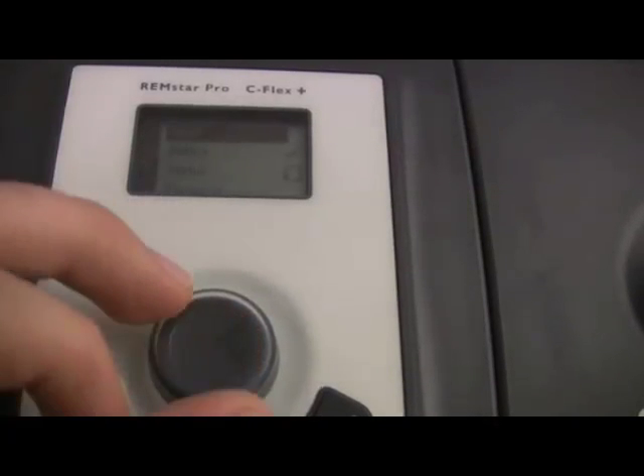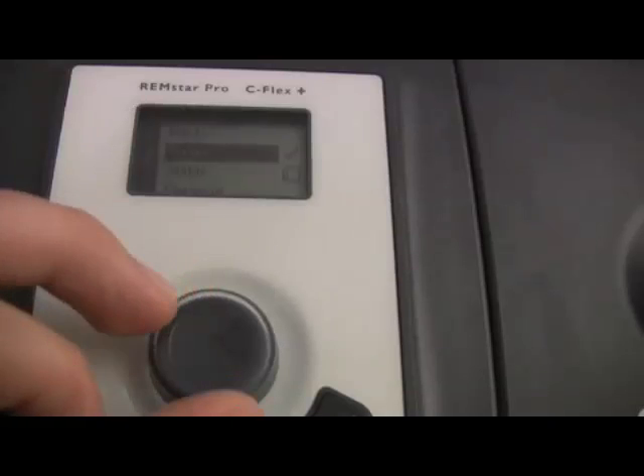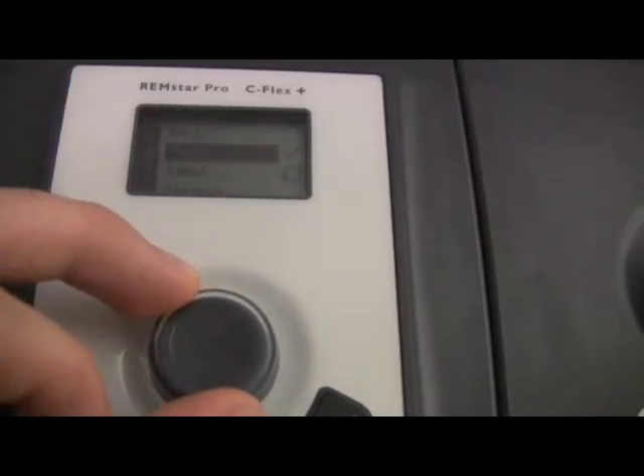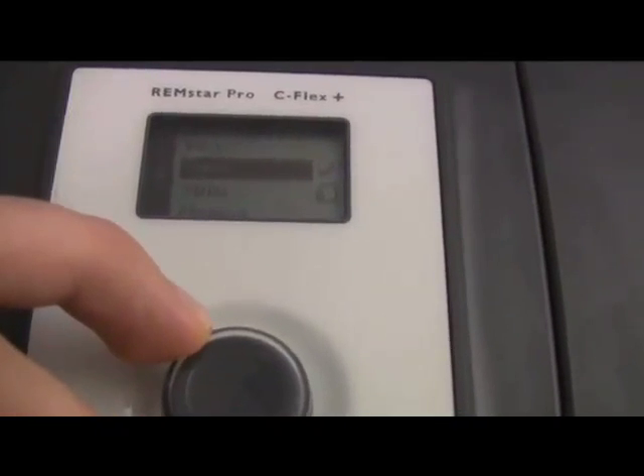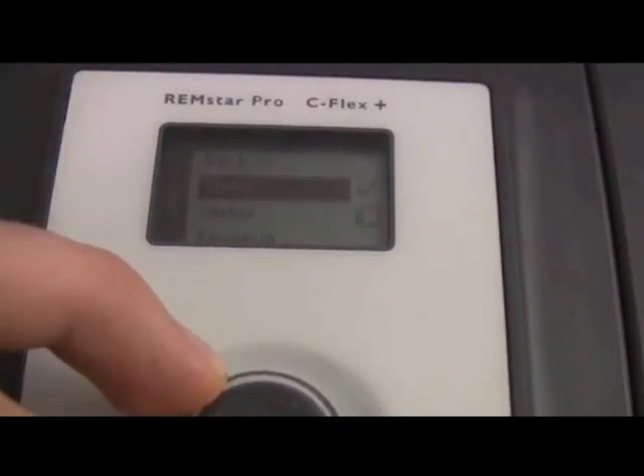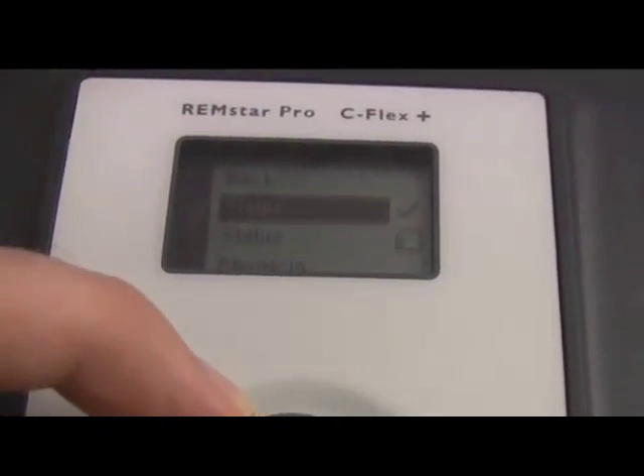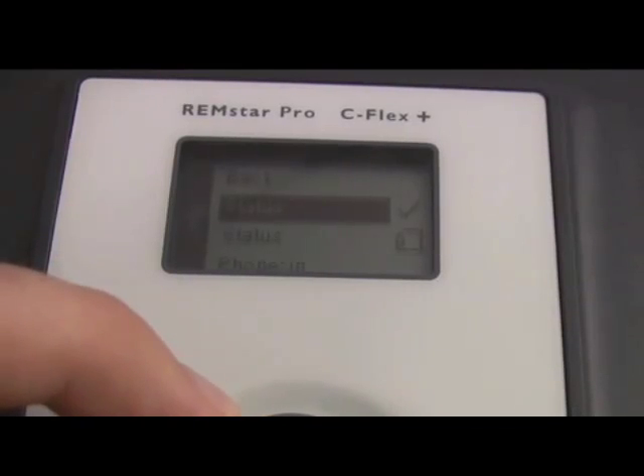You should see two status displays. The first is for the modem. If the modem status has a check mark, it is connected successfully to a live phone service. If there is no status for the modem, it is not connected properly to the CPAP machine, and you should remove the modem and reinstall it. If the modem status has an X, it is properly inserted into the CPAP machine but not connected properly to the phone line. You should check that the modem line is securely fixed in the phone jack.